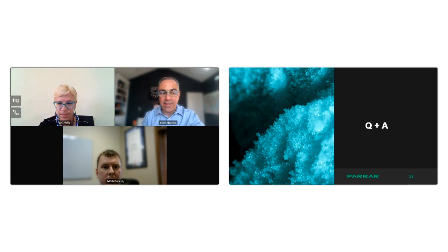We also have IQ, OQ documentation that can be performed by us or also used by a validation team in region that can validate your product as well once it's installed. Okay, thank you. Is there a specific temperature required for the area in which many ULT units may be stored? I think the operating ranges are labeled on our functional specs, but it's typically like 10C to 30C ambient conditions that the units are designed for.